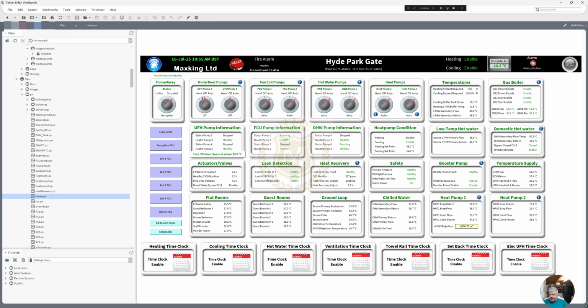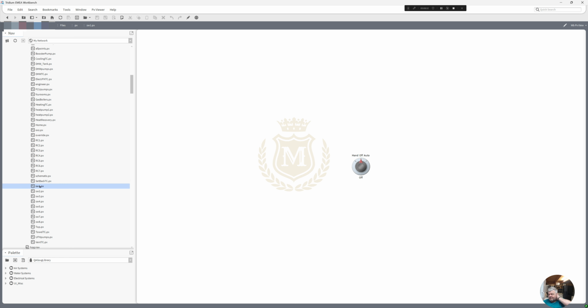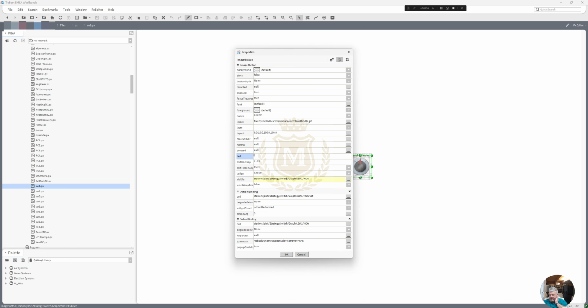We've got some switches up here, which we've got the underfloor pumps off at the moment. Let me just show you how this switch works. We click it, it goes to auto. We click it again, it goes to hand. We click it again, it goes to off. Simple as that. And how we do them switches, if I look in switch 1 there, that's a PX file for switch 1. And we have some logic here, the strategy switch, graphic was switch 1, hand, auto, off or auto set, and the action arg is set to 3, and that is just for the value binding.